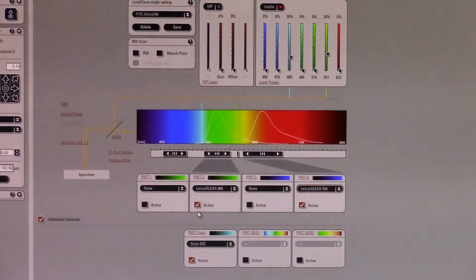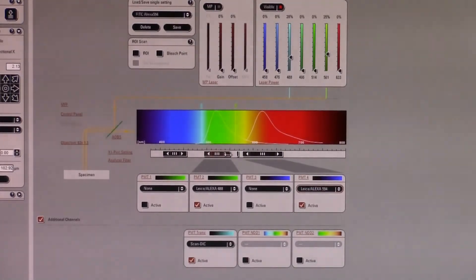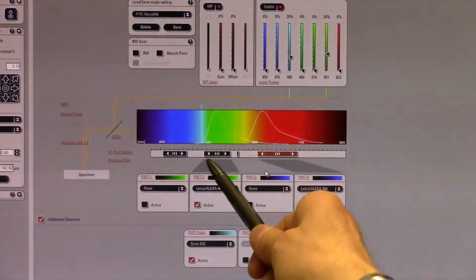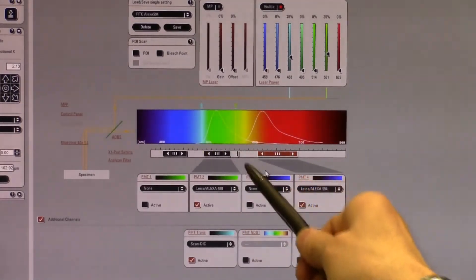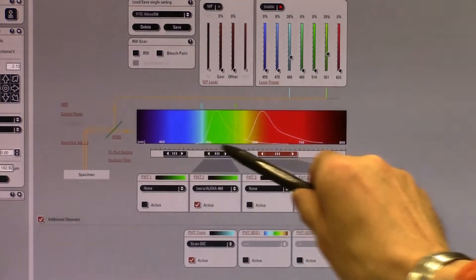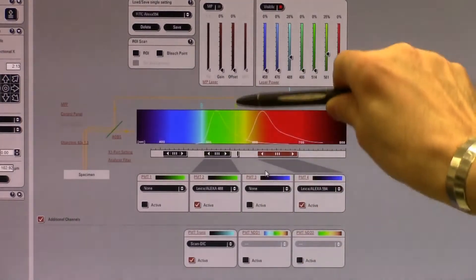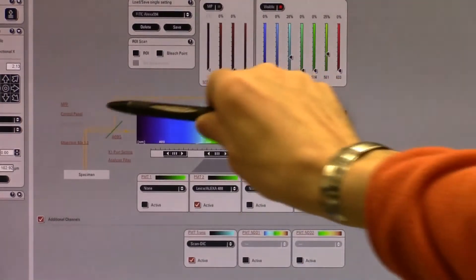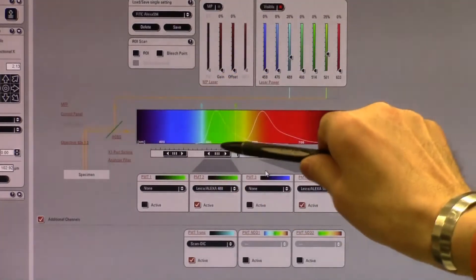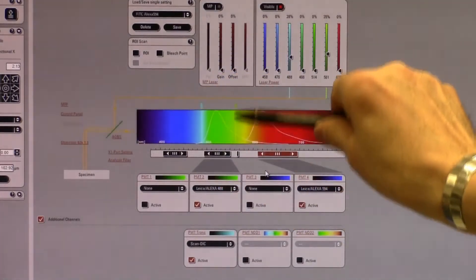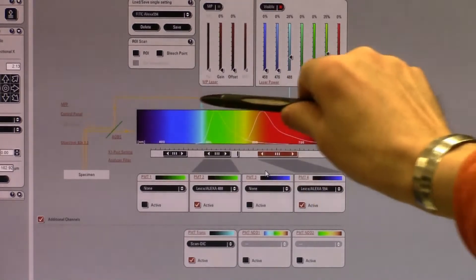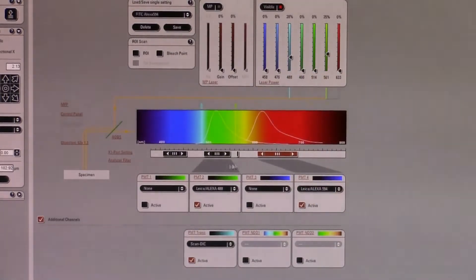We're going to make sure that our settings are correct for this. We have to make sure that when we're looking in multi-channel imaging, that our gate that we select for our fluorophore does not extend out too far past the laser line. The AOBS will control for some of this, but in addition, we want to make sure that our gate does not extend past either of these excitation laser lights.